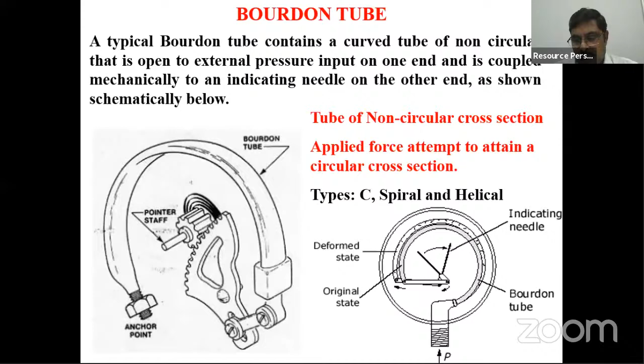When you apply the pressure, the non-circular cross section tries to become circular in shape. Therefore, there will be a bending moment, and this bending will be transmitted through the pointer through a suitable spring or gear mechanism. So with that you can measure the pressure directly. It's a direct display. By using a Bourdon tube you can measure the pressure in the range from atmospheric pressure up to maybe about 1,000, or you can also go for a few thousand bar. And there are several versions, for example, this kind of spiral one can be used for a small range.